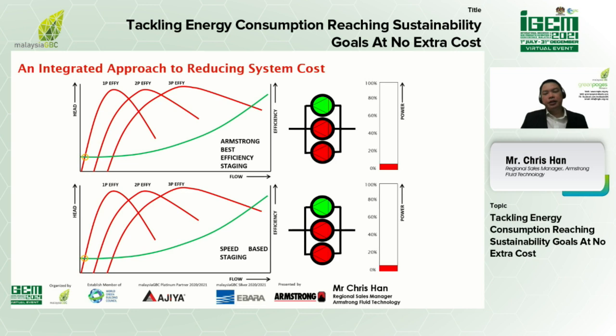However, like I mentioned, technology advances have arrived at solutions to make it much easier, whereby parallel pump controllers with best efficiency staging capabilities are starting to pay dividends. Therefore, parallel sensorless pump control is another flow control strategy for you to consider. With the rise of sensorless pump control technology, parallel pumping systems can be further optimized for improved energy savings, in areas where remote sensors are not possible or not even practical to place. And when we talk about the parallel pump approach, it is important to consider the staging methodology for the pumps.